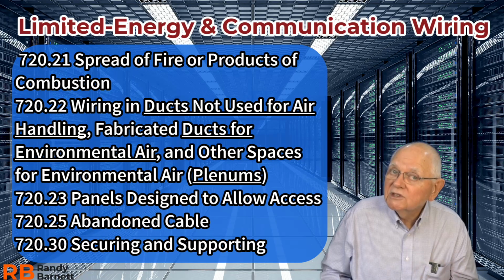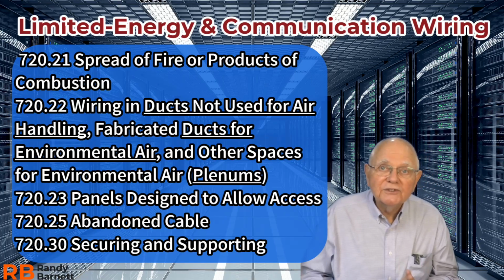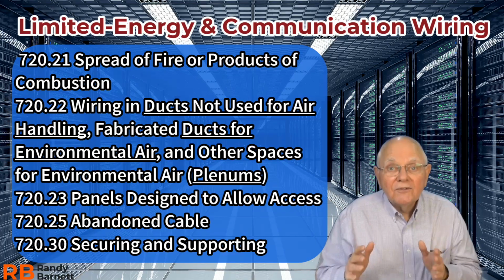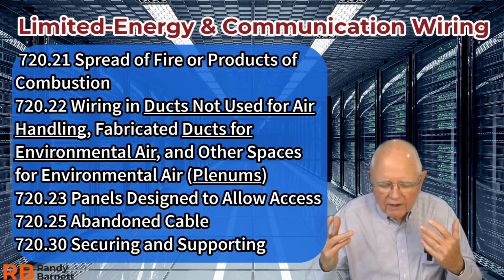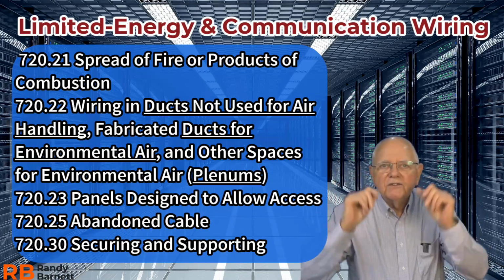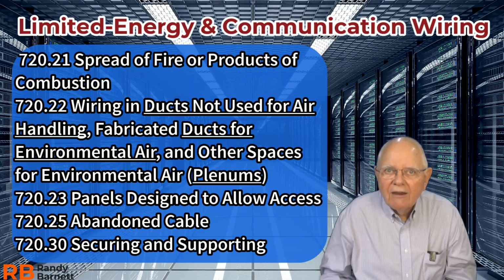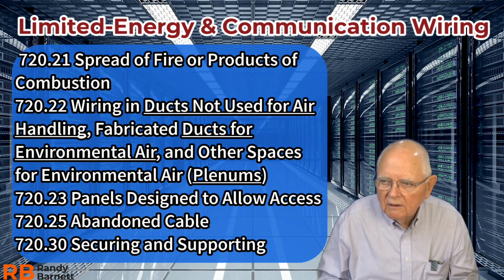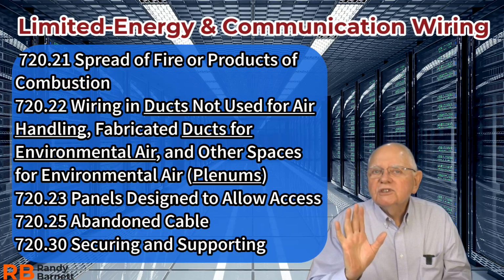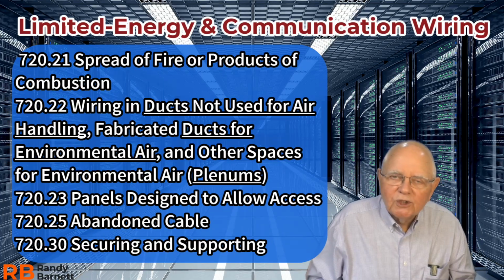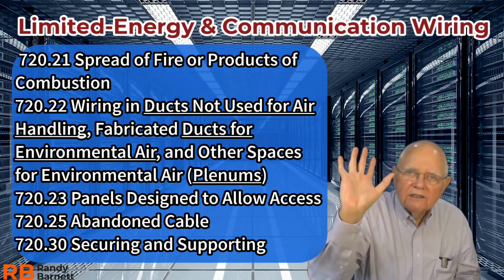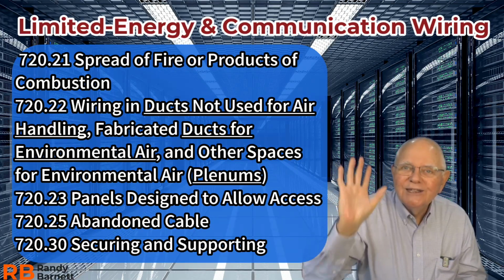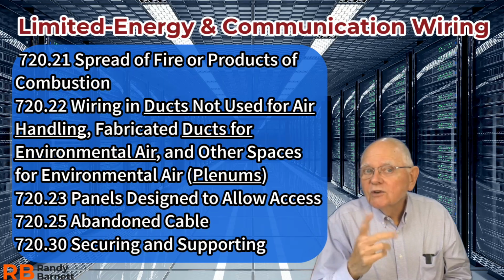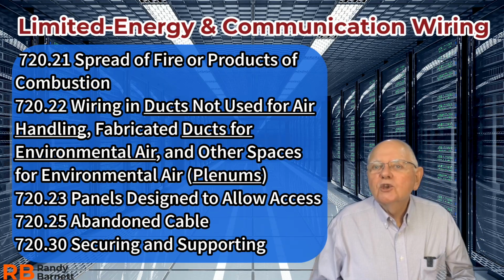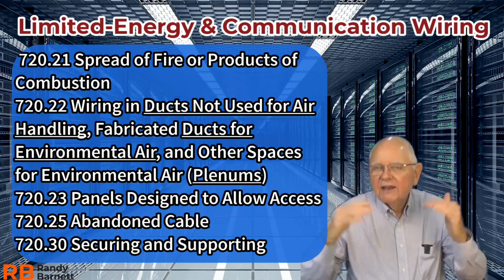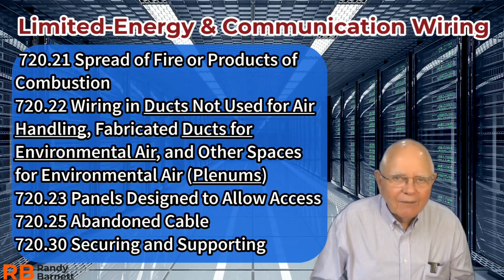720.23 ties right into what we just talked about. It talks about panels designed to allow access. If the panel is designed to allow access, and once again, as the code brings out, think about a suspended ceiling. If it's designed to allow access, it must allow access. Okay, well, hey, have you ever pushed up on one of those ceiling tiles, maybe in a commercial building somewhere, and you get it up about 1 inch, and okay, you're hitting some duct work or something like that. Also, it tells us I can't allow for any accumulation of cables on those panels on the top. And I know you've never seen that happen before, right?